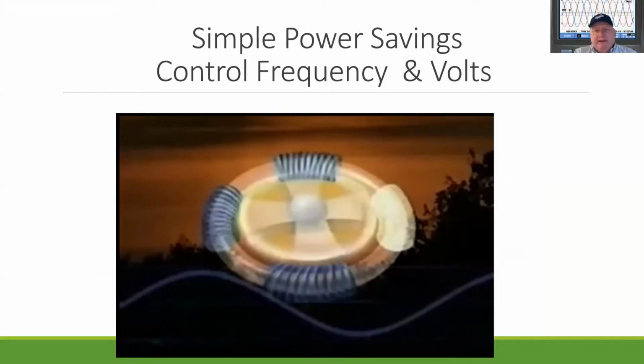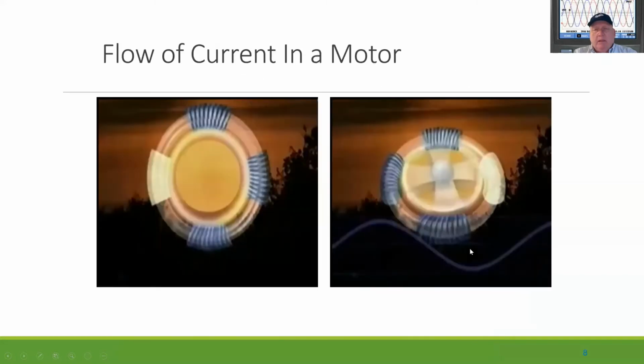So what I want to start out with today is that the electric motor is basically a rotating field that comes from our 60 cycle power. You see down below here the sine wave of voltage from your power lines, and there are 3 of these that feed typical motors for water pumping. The key is that the motor is going to run at fixed speed, and when it's starting it wants to jump immediately to that fixed speed, because this sine wave is pretty much permanent coming off the generators. So the generators are producing the power at 60 cycles a second.